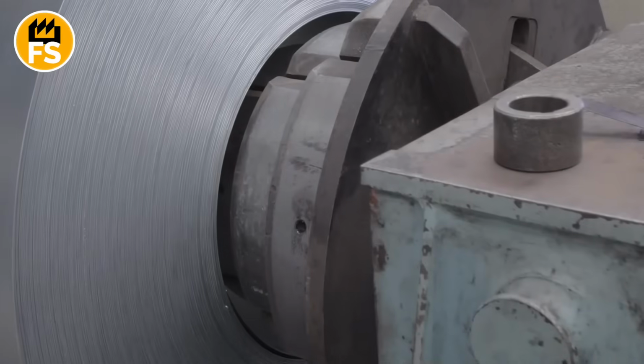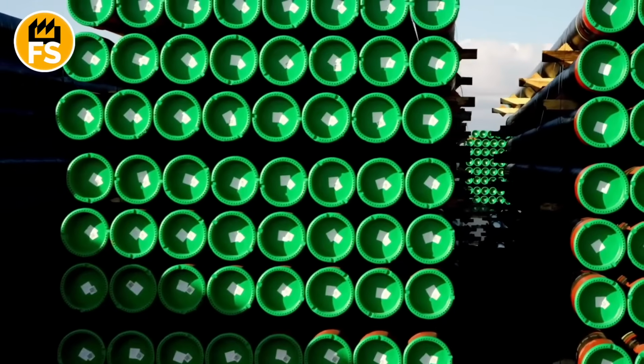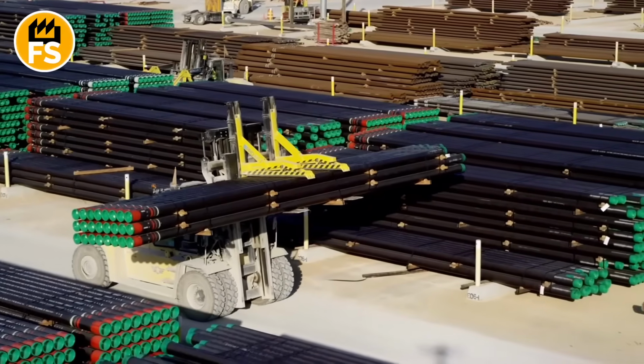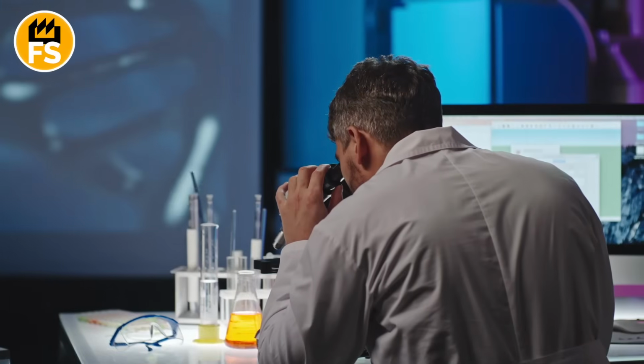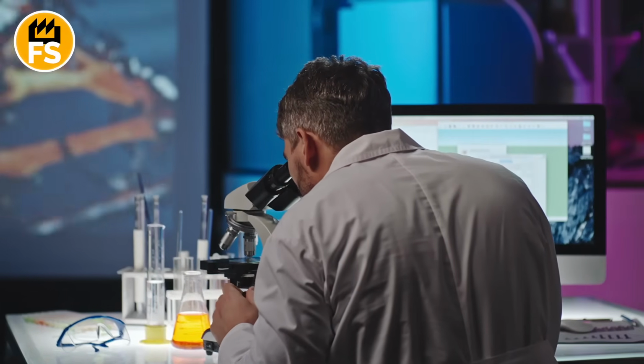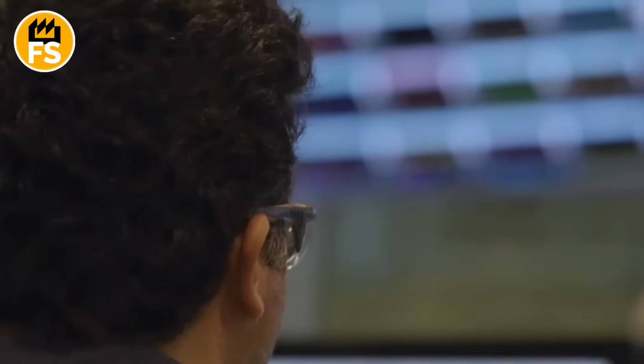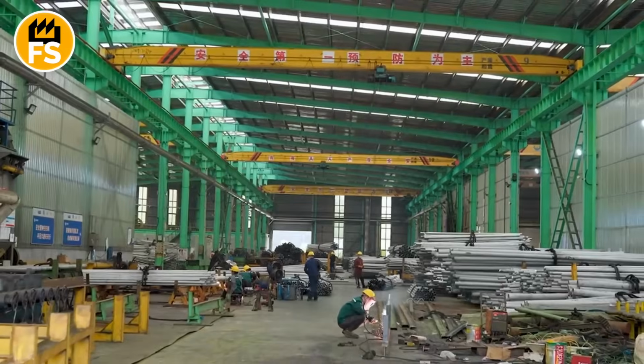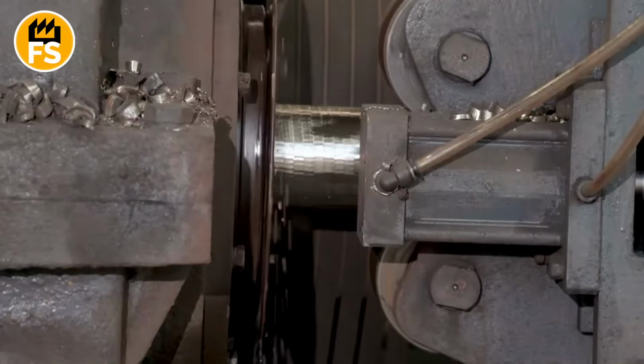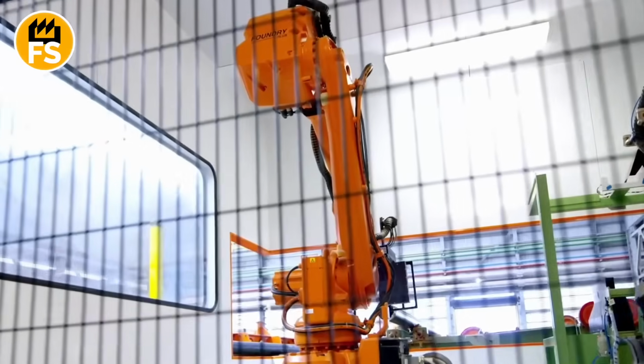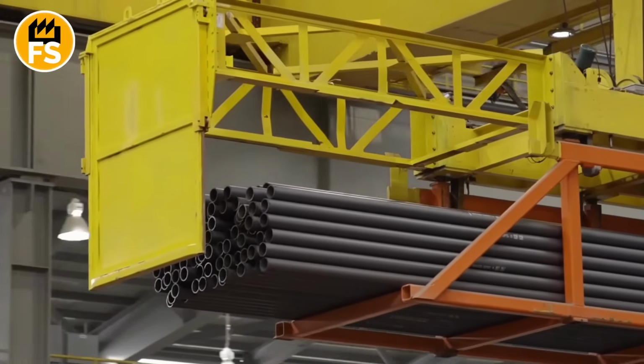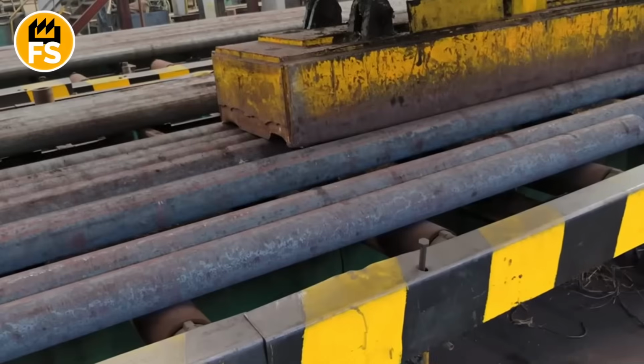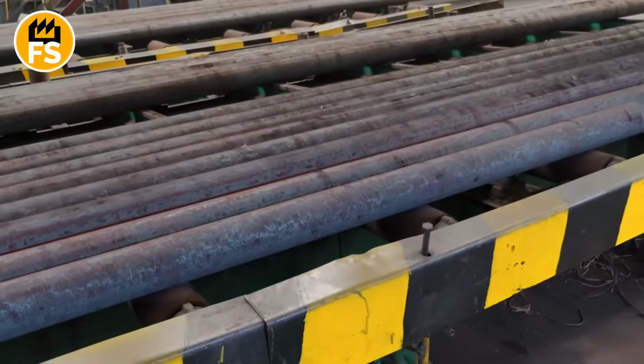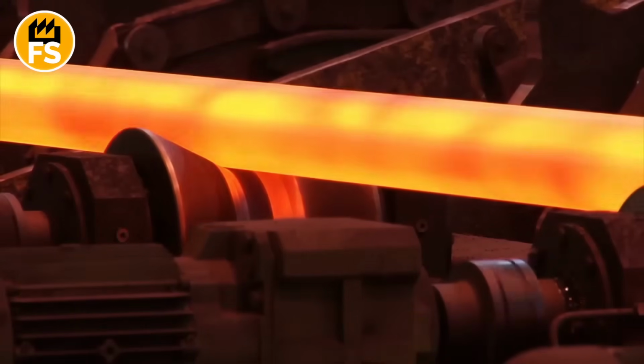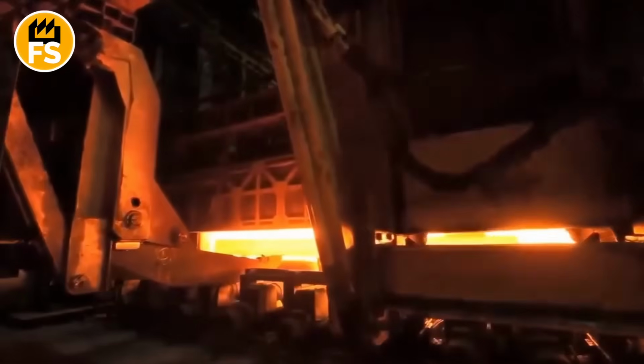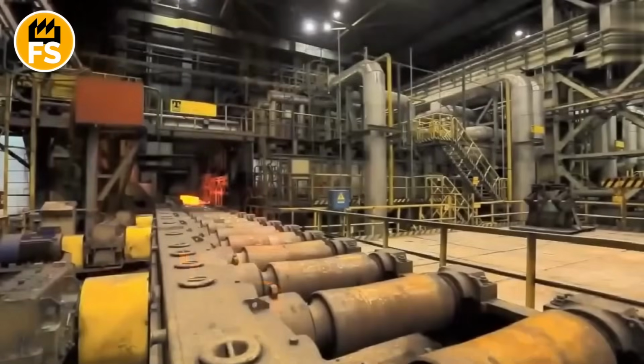Each chemical element glows uniquely, so the device recognizes exactly which elements are present in the steel and in what quantities. How much carbon, manganese, chromium, nickel, or phosphorus. This analysis takes only a few minutes, but provides a complete picture of how well the billet meets technical requirements. If the composition isn't perfect, the batch might be rejected or redirected to other production lines. From 1 to 3% of billets are sent for remelting. Defective billets are sent to an electric furnace with a temperature of 2,900 degrees Fahrenheit, where the steel becomes liquid again. All the post-melting slag is used for road construction.